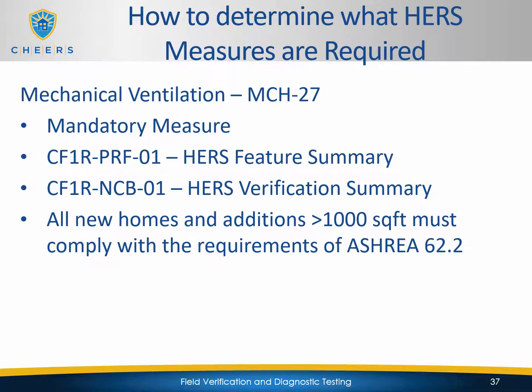Mechanical ventilation on the MCH-27 is a mandatory measure. You're going to find that on the CF1R Perf 01 in the HERS feature summary, or the NCB 01 in the HERS verification summary. And so it applies as a mandatory measure to all new homes and additions greater than 1,000 square feet. And these must comply with the requirements of ASHRAE 62.2. So they're going to require an indoor whole house mechanical ventilation system.